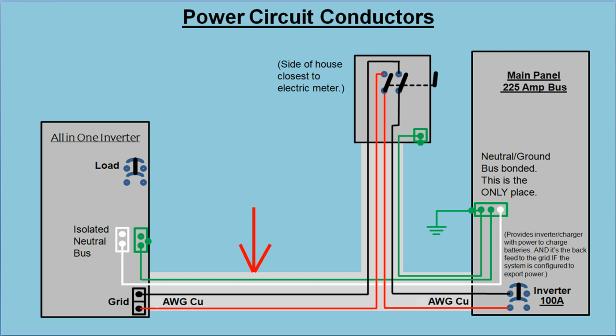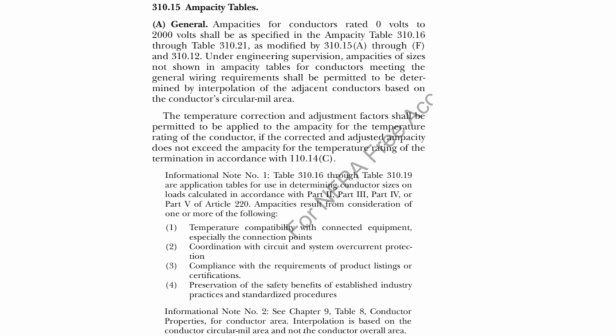Now moving ahead, there are 3 current carrying conductors in this section of conduit. There are also 3 current carrying conductors in this section of conduit. But there are 4 current carrying conductors in this section of conduit. And this section is probably going to be over 10 feet long. Let's look at the National Electrical Code. If you're currently learning the code, you might want to crack open your NEC book and follow along. If you don't have a book, check out my previous video about free online access to the NEC.